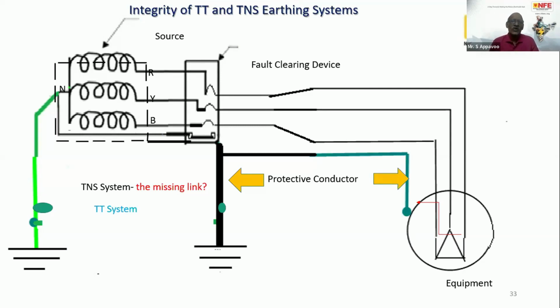Because of which we have to provide some other measures like core balance CT and earth fault relay and everything. So the thing is, we have to ensure the correct earthing system according to the type of installation. If it is an explosive, highly explosive area, then you devise an IT system or TT system. There is no strict hard and fast rule. But 99% of the accidents that do occur can be contained by the TN-S system only.